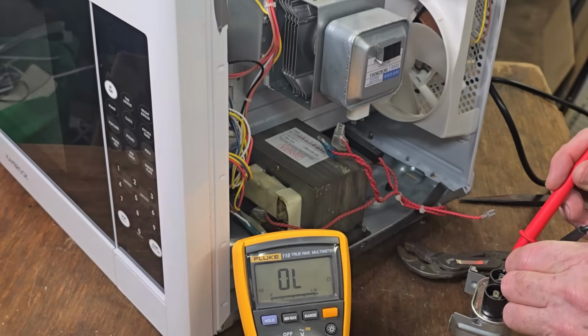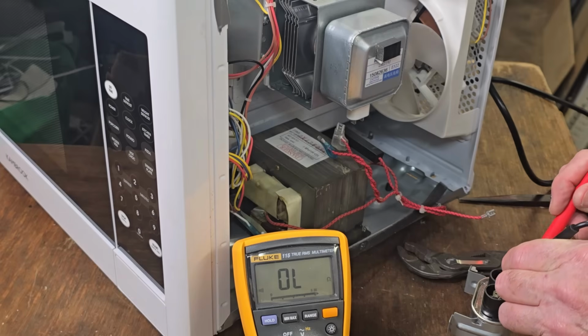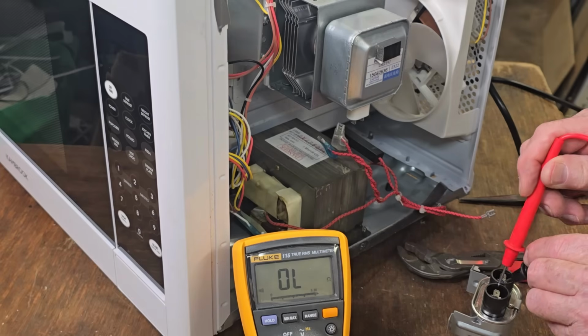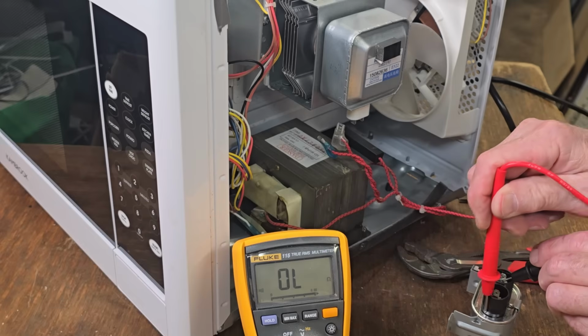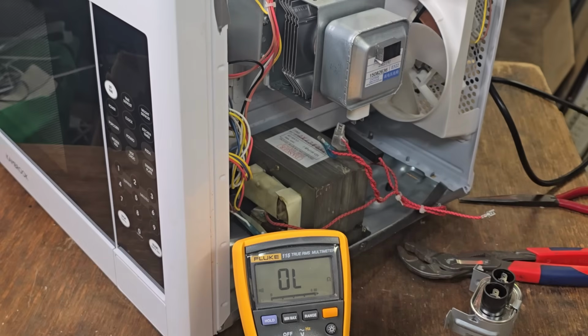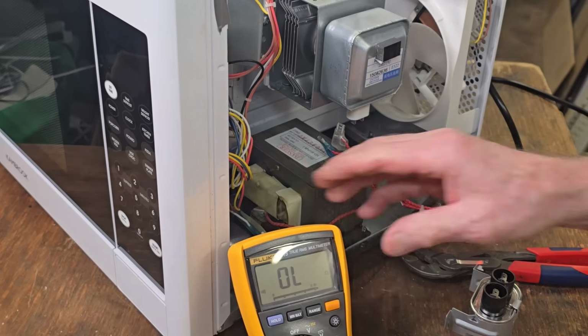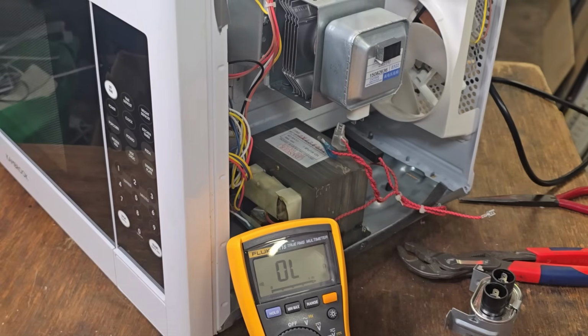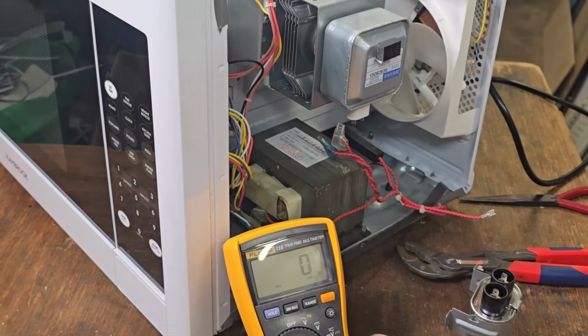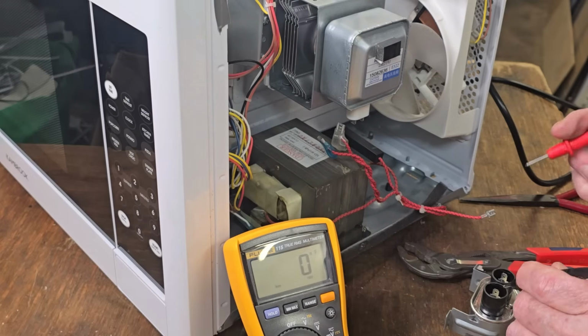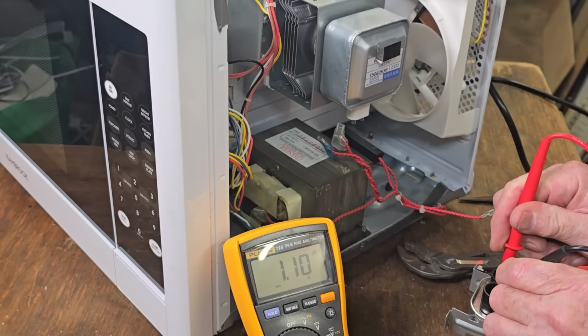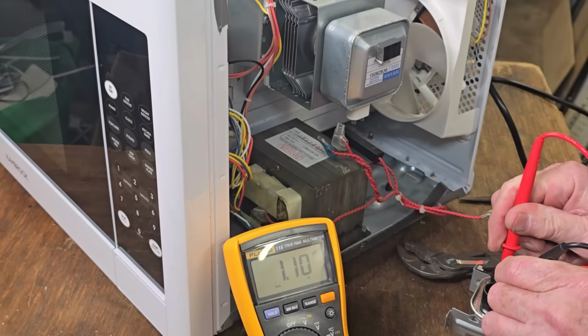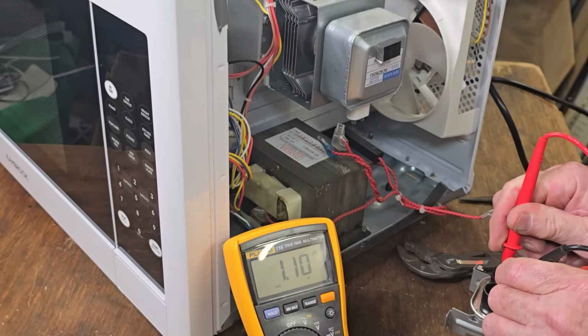No continuity across here, and none to the case. A little bit of a beep when changing polarity, so that looks good. Let's check that out on our actual capacitance reading and see what it gives us. It's 1.05 by the case, 1.1, that's exactly the same as what the other ones gave me.